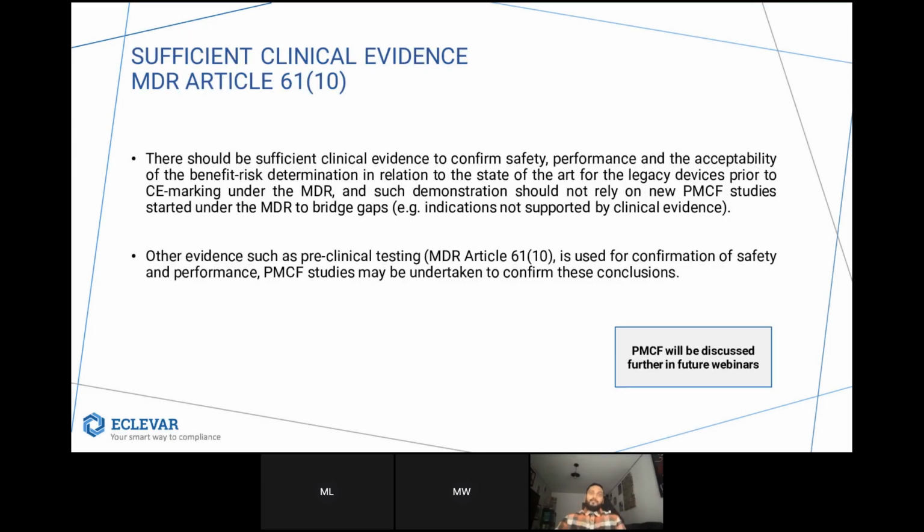Sufficient clinical evidence, following MDR Article 61(10). There should be sufficient clinical evidence to confirm safety, performance, and acceptability of the benefit-risk determination. As Max has said, in relation to the state of the art for the legacy devices prior to CE marking under the MDR. Other evidence, such as preclinical testing, is used for confirmation of safety and performance. PMCF studies may be undertaken to confirm these conclusions.